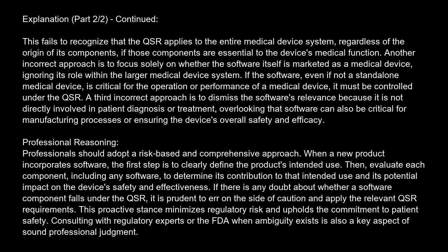When a new product incorporates software, the first step is to clearly define the product's intended use. Then, evaluate each component, including any software, to determine its contribution to that intended use and its potential impact on the device's safety and effectiveness.